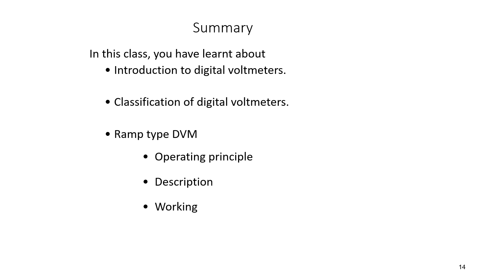So just to brief up, the ramp type digital voltmeter principle is that it is based on the measurement of the time that a linear ramp voltage takes to change from 0 to the level of the input voltage or to decrease from the level of the input voltage to 0. This time period is measured with an electronic time interval counter, and the count is displayed as the number of digits on an indicating tube or the display.